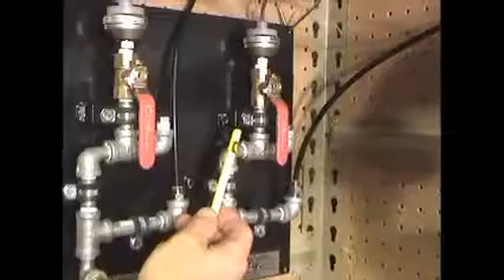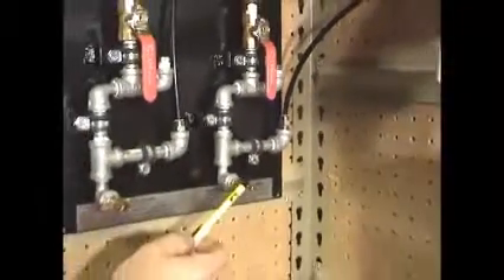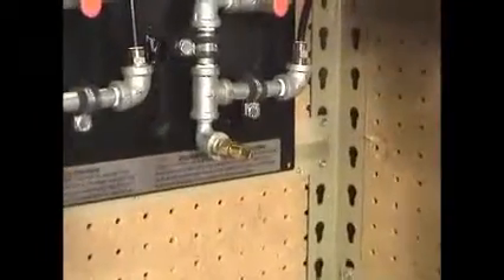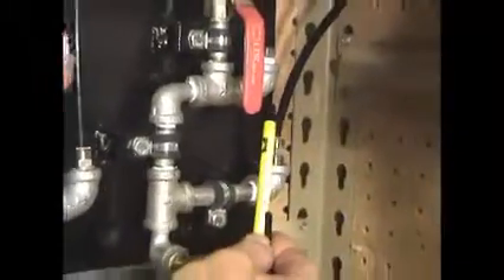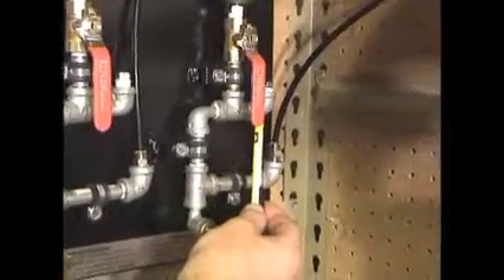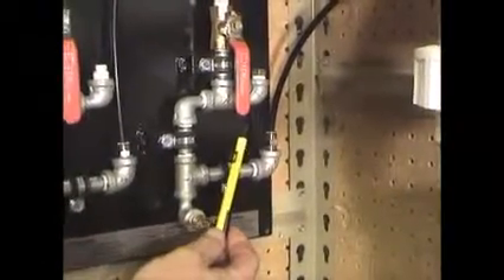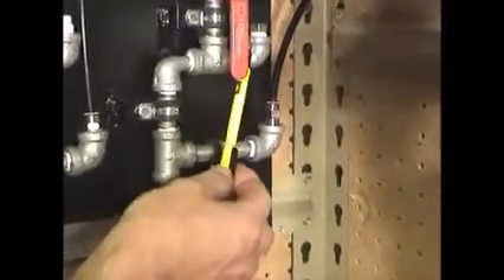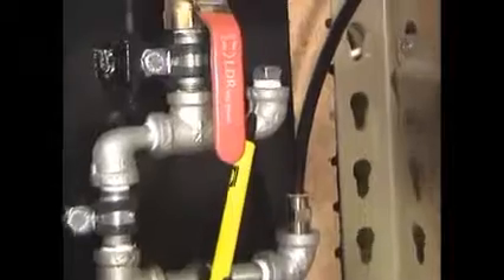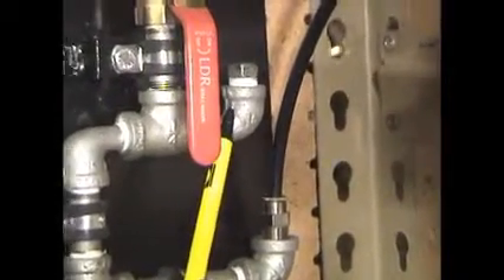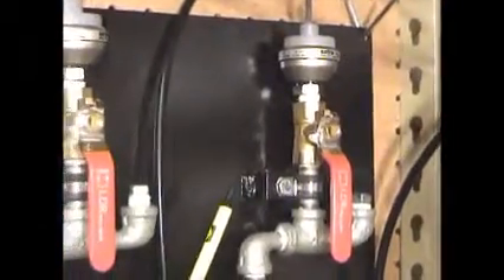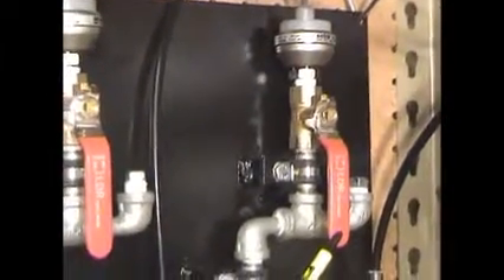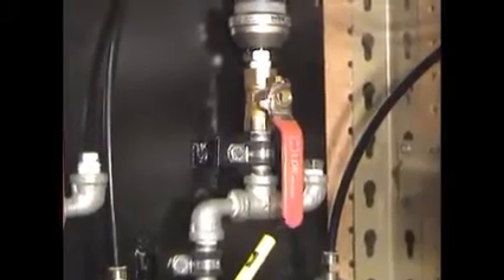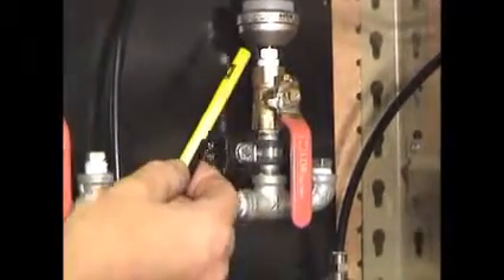The manifold on the right-hand side contains a discharge line pressure transducer, an on-off ball valve, and a drain valve. A pressure line coming from a discharge standpipe located on the main pump discharge line is attached to the lower manifold elbow. The top elbow has a plug installed and can be removed and replaced with a hose going to a mechanical pressure gauge if desired. During operation, make sure the ball valve handle is positioned down or in the open position so pressure can be introduced into the pressure transducer.